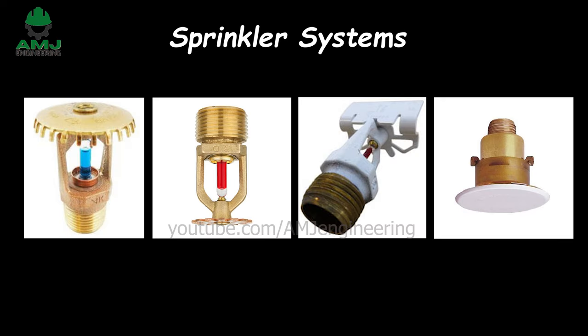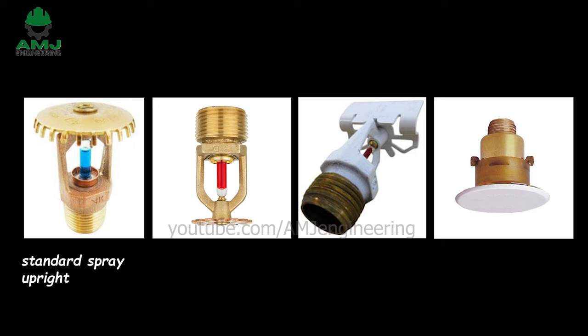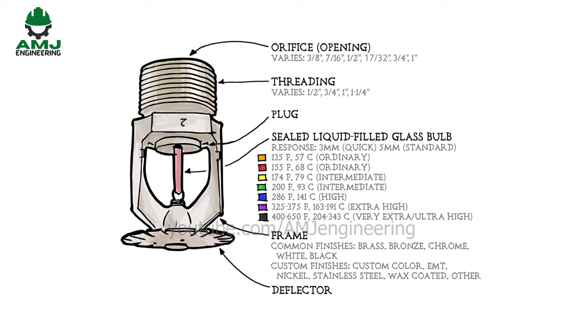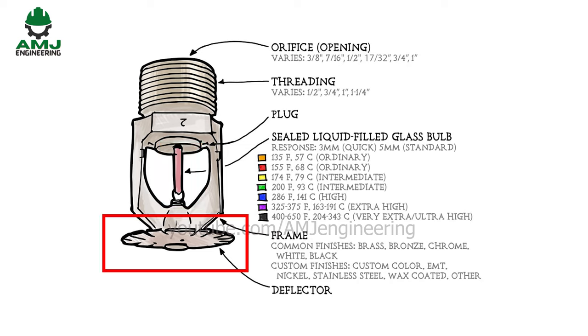Sprinkler systems. When it comes to the sprinkler head itself, the four most common styles are: standard spray upright, standard spray pendant, sidewall sprinkler, and concealed sprinkler head. Nearly all fire sprinklers are composed of the same components: a sealing assembly or plug that prevents water from escaping, a heat-sensitive element that allows water to flow at a given temperature, a deflector that distributes water effectively, and a frame.